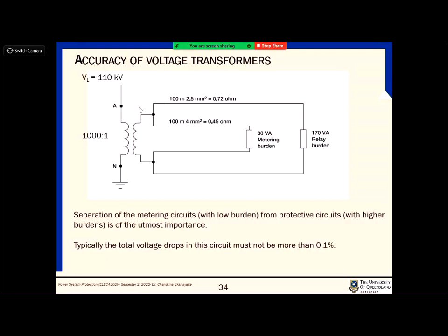And then the other important thing is that when you have, let's say, protection relay and metering, we are not connecting them to the same line. As an example, another cost-effective way is that you connect this one here, 170. That is another way, right? Parallel connections. Low cost, right? But this is a wrong configuration.